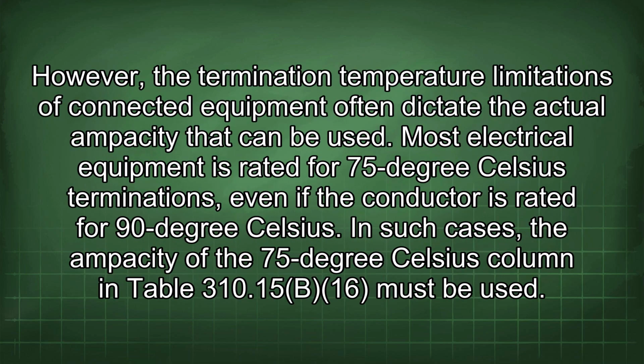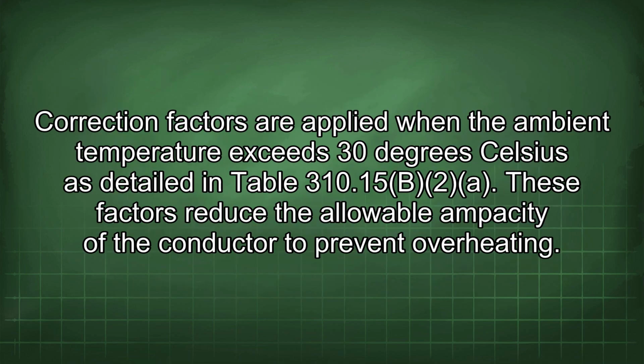However, the termination temperature limitations of connected equipment often dictate the actual ampacity that can be used. Most electrical equipment is rated for 75 degrees Celsius terminations, even if the conductor is rated for 90 degrees Celsius. In such cases, the ampacity of the 75 degrees Celsius column in Table 310.15(B)(16) must be used. Correction factors are applied when the ambient temperature exceeds 30 degrees Celsius as detailed in Table 310.15(B)(2). These factors reduce the allowable ampacity of the conductor to prevent overheating.